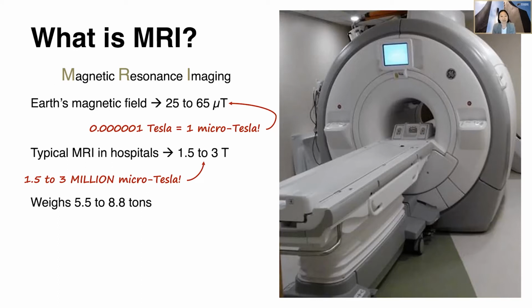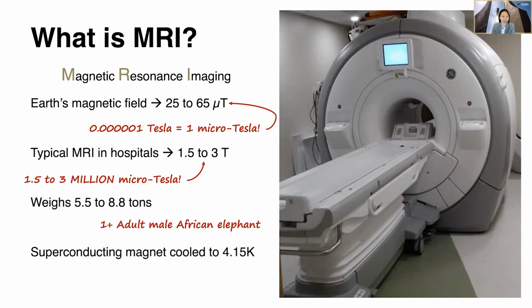Also, it's a hefty machine. It weighs about 5.5 to 8 tons. And a lot of that weight is actually because it has to contain liquid helium. You need the liquid helium because you have to cool the superconducting magnet down to 4.15 Kelvin, right? And that's really, really cold. It's equivalent to minus 269 degrees Celsius, or about minus 452 degrees Fahrenheit, right?